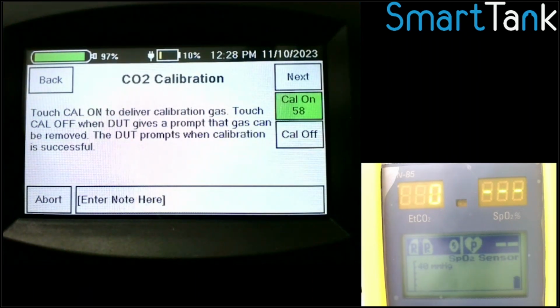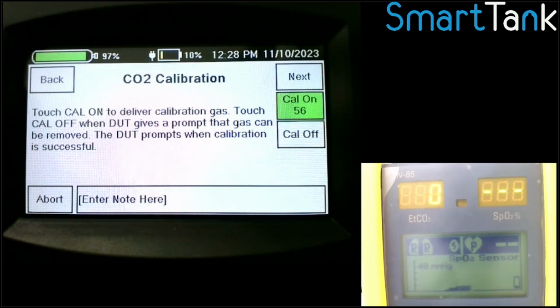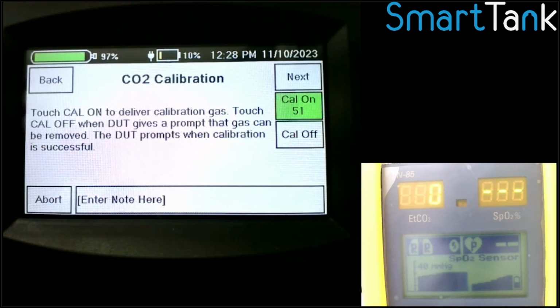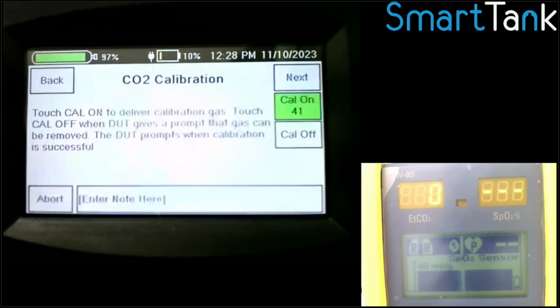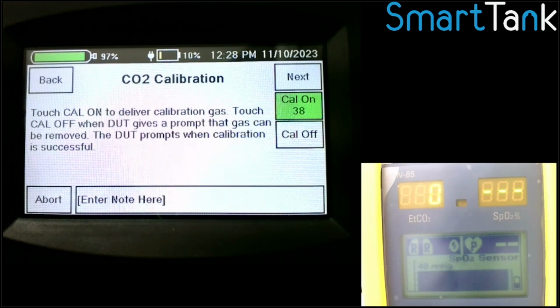So if you watch the yellow device over here, you'll actually see that it's getting gas now. And so the SmartTank has in it a manifold that brings it down to room pressure, and it delivers just the right amount of gas for this capnometer. That's one of the things we really wanted to do, was to design the SmartTank so it'd save as much gas as possible. So remember, we measured it at 47 milliliters a minute. So it's delivering about 50 milliliters a minute right now. If this device wanted 200 milliliters a minute, we'd deliver about 203 milliliters a minute. And so by doing that, we use the very bare minimum amount of gas that's needed to do these calibrations.